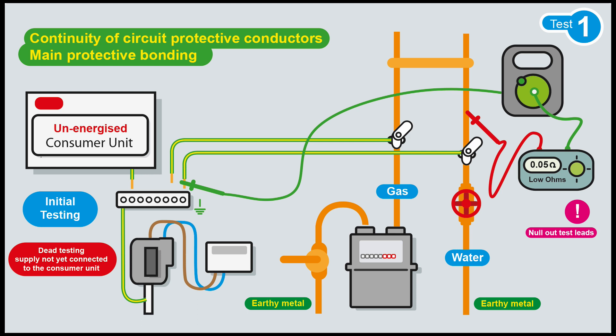Now where would it be useful to know that? It'd be useful when you're testing one conductor, such as your main protective bonding conductors, which is generally done with the long lead method. And there's no regs on any numbers you should be getting, but there is guidance that it should be below 0.05 of an ohm.